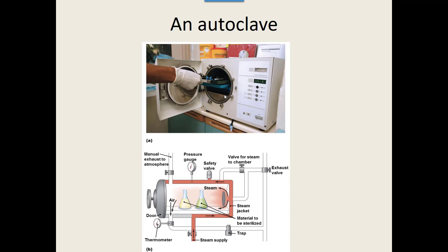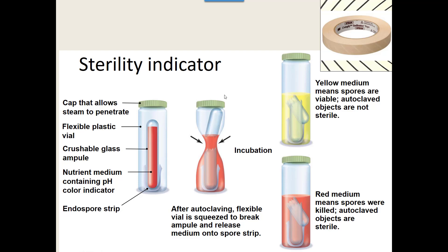To ensure the autoclave actually worked, there has to be some type of indicator, because you don't know if it reached the correct temperature for the correct amount of time. There are vials with an endospore strip that go in with what you're autoclaving. Getting up to temperature and pressure, maintaining it for 15 minutes, and cooling back down is usually about a two-hour process. If the fluid in the vial is yellow, the spores are viable — meaning the autoclave didn't reach the correct temperature or time. If it's red, everything worked.